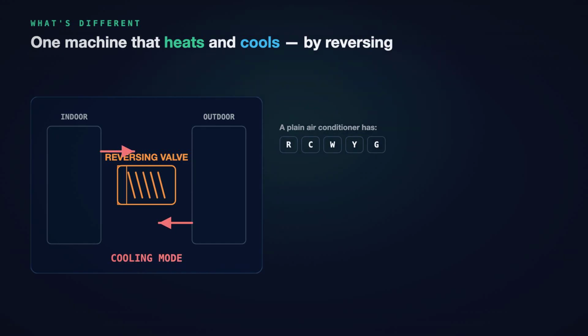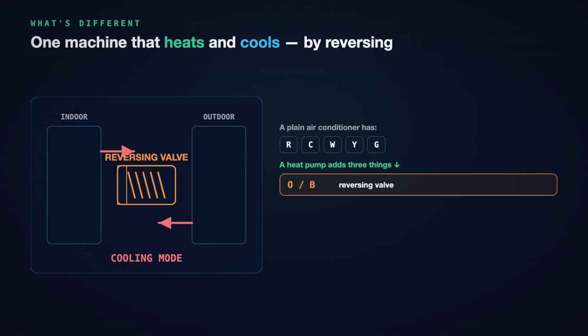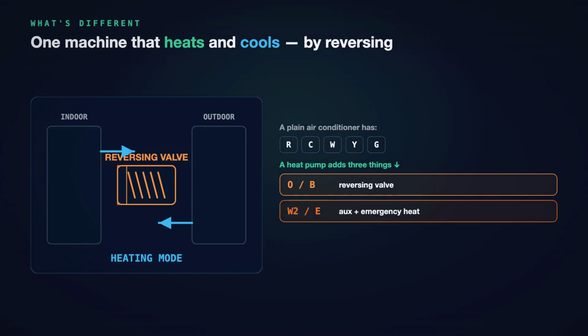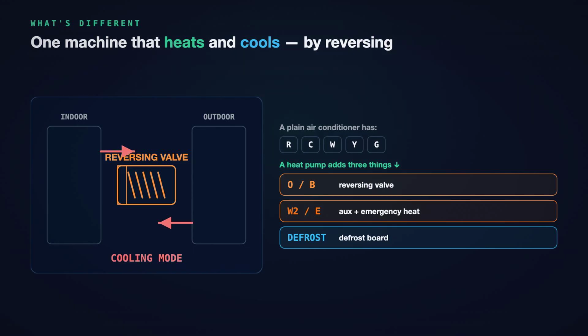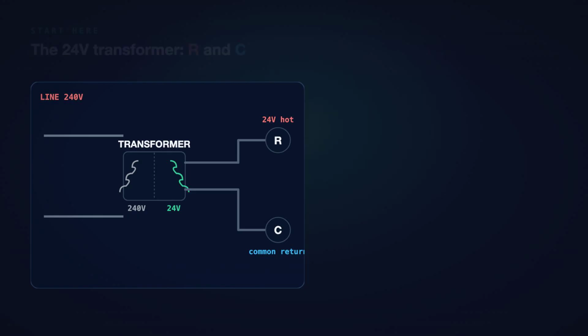A plain air conditioner gives you R, C, W, Y, and G: power, common, heat, cooling, and fan. A heat pump keeps those, then adds three things. A reversing valve terminal, called O or B, to flip between heat and cool. Auxiliary and emergency heat, W2 and E, for backup. And a defrost board out at the unit. Learn those extras, and the whole print opens up.